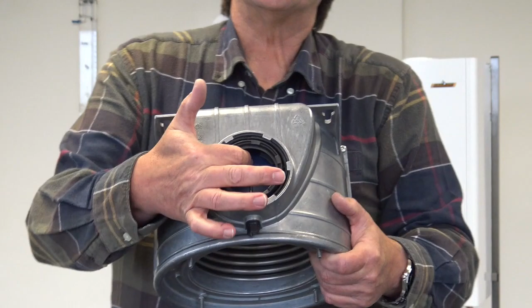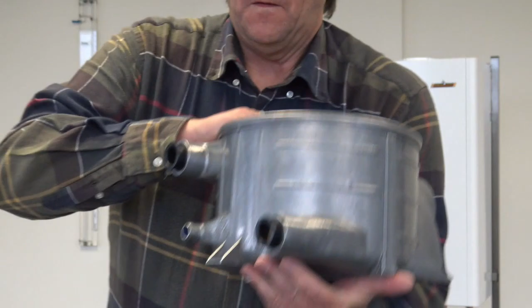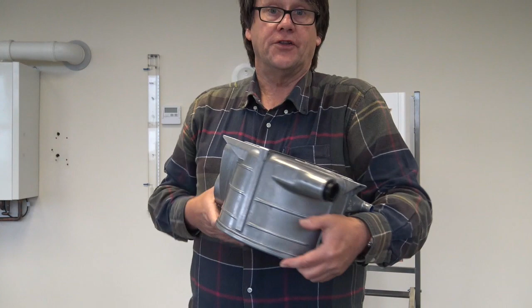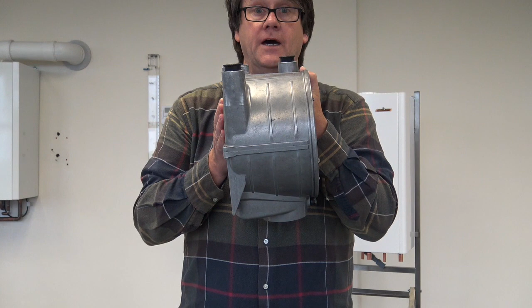Inside we have a shroud, and that shroud stops the bulk of the condensate getting to the die-cast aluminium. Not sand cast, die-cast, okay? Flow and return at the bottom, cannot airlock. It pushes, it pulls, okay? But the biggest winner with this heat exchanger for you lads, you guys, sorry, is there is no plastic connected to that heat exchanger, okay? No flue headers at the back, no sumps at the bottom, nothing that's going to melt and nothing that's going to case harden. That is the heat exchanger, okay?